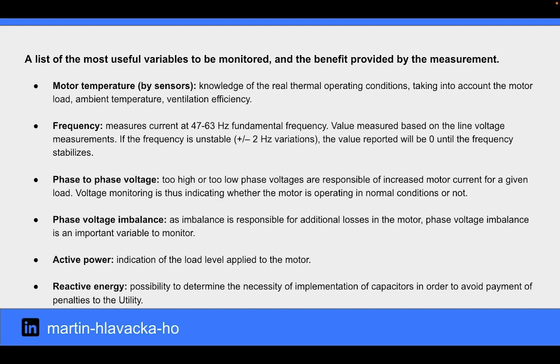Frequency measures current at 47 to 63 Hz fundamental frequency. The value measured is based on the line voltage measurements. If the frequency is unstable, the value reported will be zero until the frequency stabilizes. Phase-to-phase voltage. Too high or too low phase voltages are responsible for increased motor current for a given load. Voltage monitoring is thus indicating whether the motor is operating in normal conditions or not.